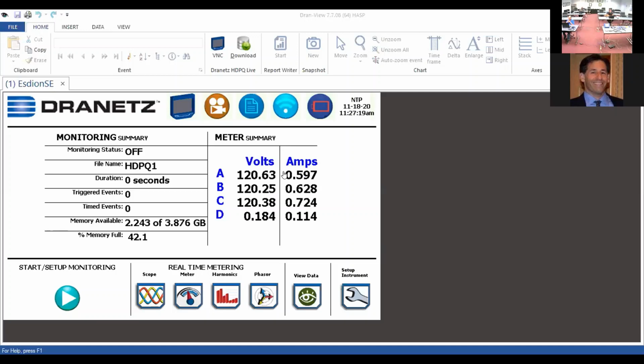So the first approach that I want to take, and this is the most common, I would call it an out-of-the-box type of setup. You don't really have to get into a lot of menus and things of that nature, and that's all in the instrument design, where I can literally take the instrument out of the box, connect it to a circuit, and run this mode, which we call automatic setup, which will set up the instrument automatically for a given monitoring scenario. It's just a minimal amount of information that you have to enter into the instrument to complete the monitoring setup. And so we're going to do that now by simply going to the start monitoring setup icon here. It looks like the play button on a tape recorder or similar device.